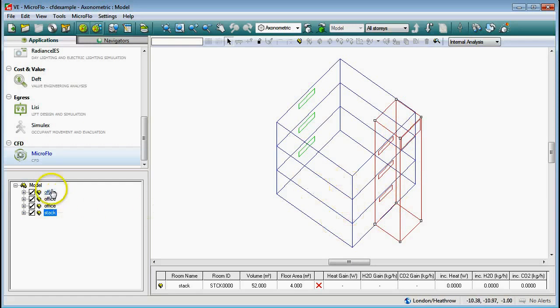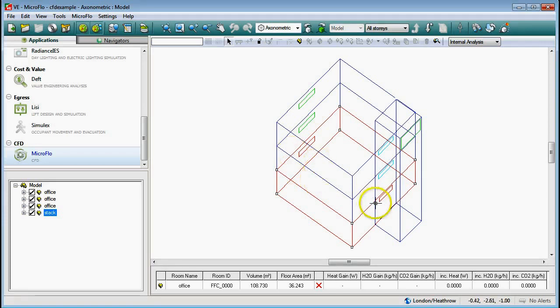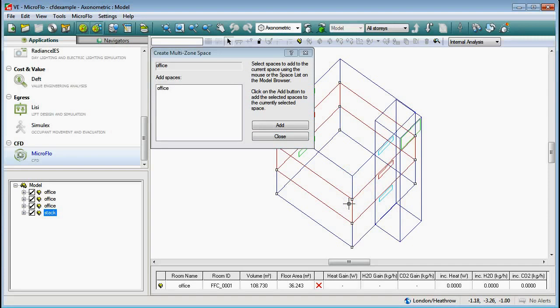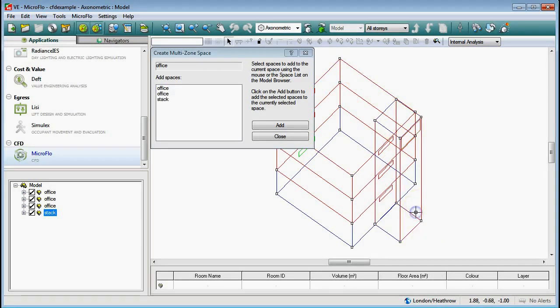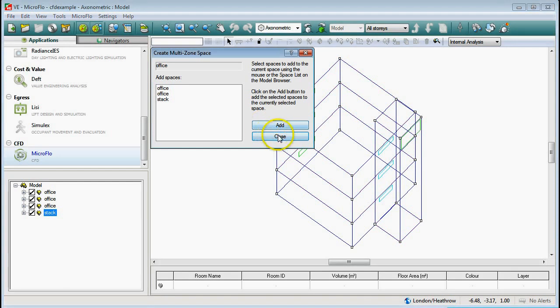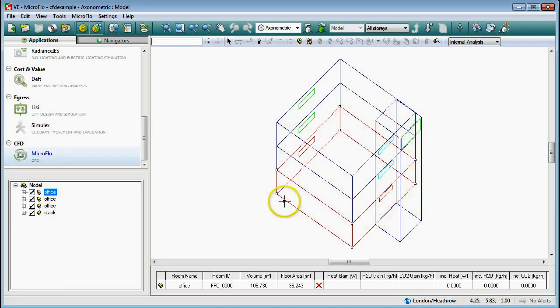I've got three office rooms and a stack listed on the left-hand side. I'm going to select the ground floor and join the first floor, second floor, and stack to it. The join button up here allows me to create a multi-zone space. I left-click that, click the first floor, hold down the control key, click the top floor and the stack, then go Add and Close. That has made a single zone out of the three rooms and the stack.